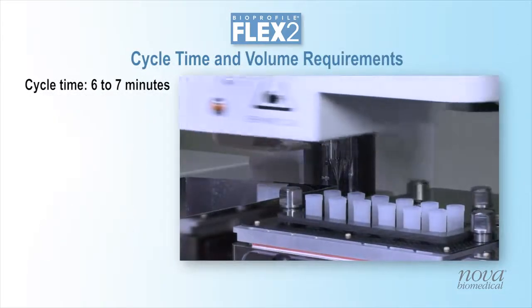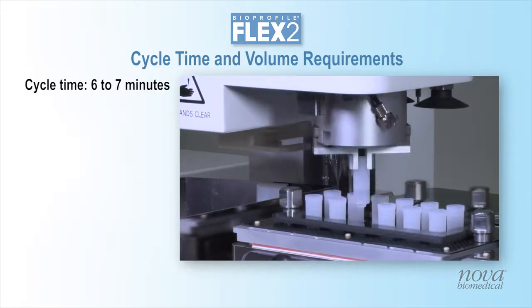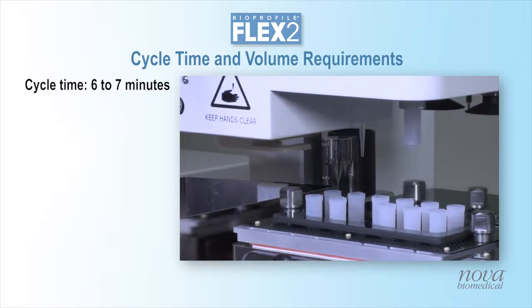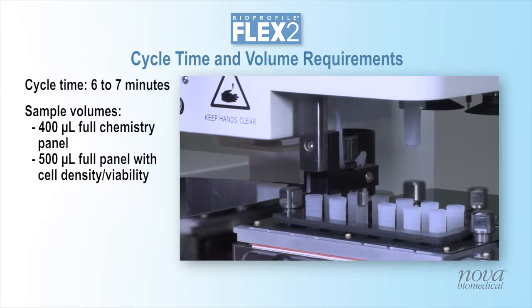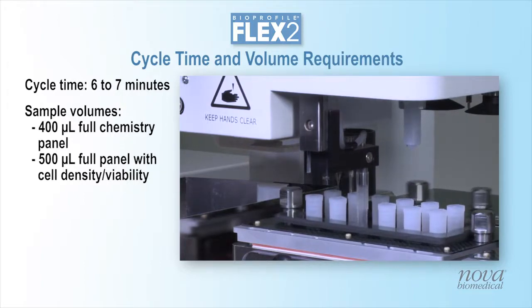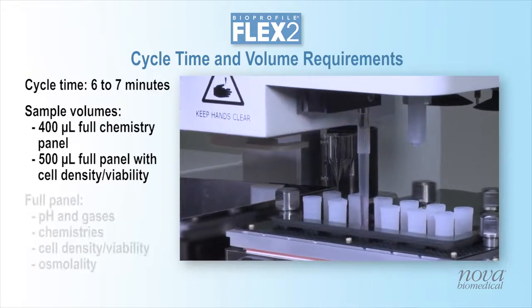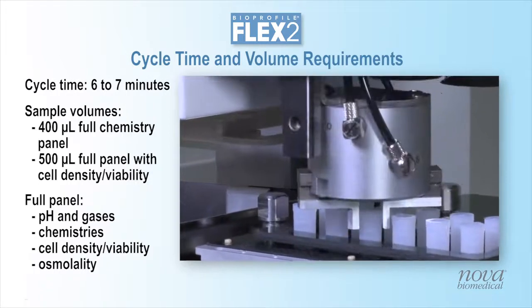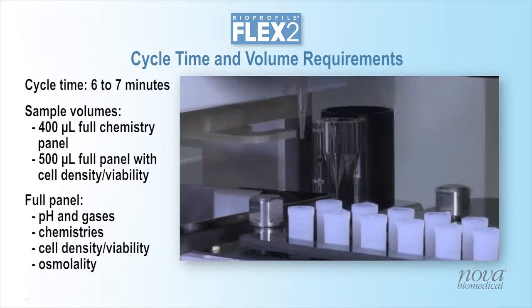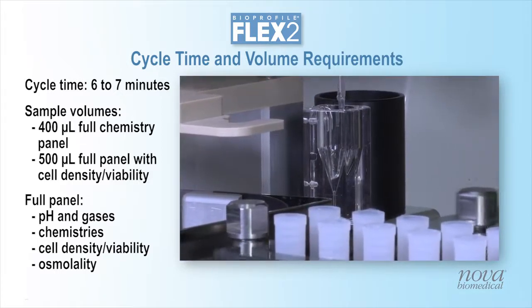The cycle time of the integrated system, including sampling and testing, is 6 to 7 minutes, depending on the configuration of tests selected. Volume preservation is critical for small volume culture systems. The maximum volume taken from each microbioreactor is 400 to 500 microliters. In most cases, this enables daily sampling of each microbioreactor while providing results for all measured tests, including pH, gases, chemistries, cell density and viability, and osmolality.